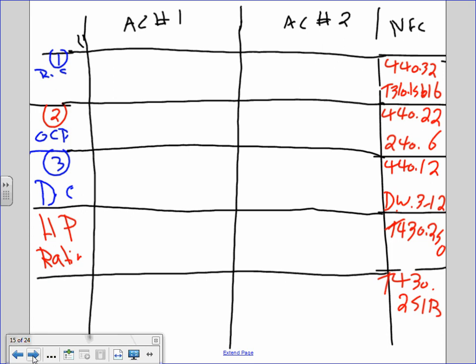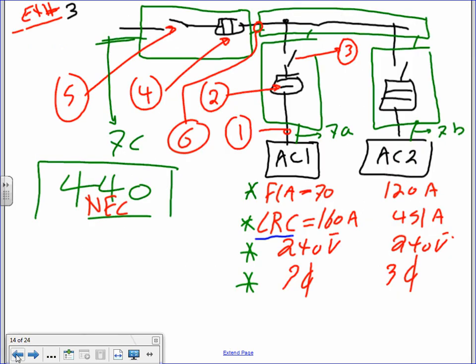The first thing to size is the branch circuit. Chillers and AC units, like motors, are continuous loads. So what do you do when you size for a continuous load? You multiply by 1.25. Now notice there's no horsepower for these chillers — they don't give them in horsepower. They're given in tons, which converts to KVA, which converts to a full load amp. They use full load amps — typically no horsepower on this equipment.